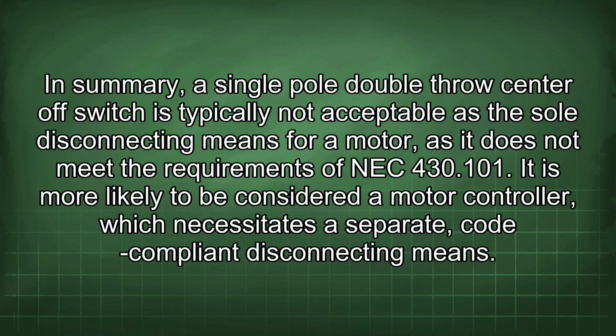In summary, a single-pole double-throw center-off switch is typically not acceptable as the sole disconnecting means for a motor, as it does not meet the requirements of NEC 430.101. It is more likely to be considered a motor controller, which necessitates a separate, code-compliant disconnecting means.